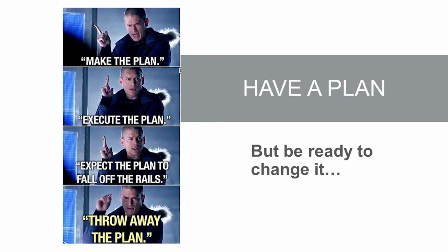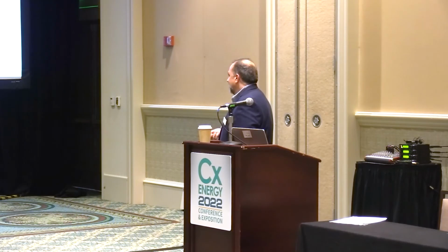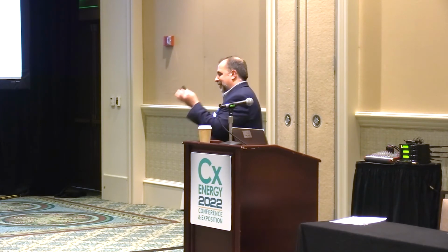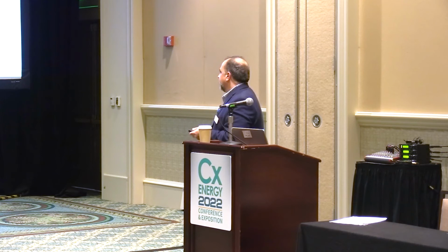And of course, the commissioning plan. I'm a big fan, imagine that, of having the commissioning plan be an indication of how you're going to actually do the functional testing. Apparently that's not always how it works, but all those surprises I've talked about, which we see on jobs a lot, mean I'm updating the test on a semi-regular basis as we go from the design to the submittals to, okay, we showed up and it's still not configured the same way. So I'm adapting and tweaking the plan, in this case for the main tanks, the supply pumps, the day tank, and the return pumps, as we go.